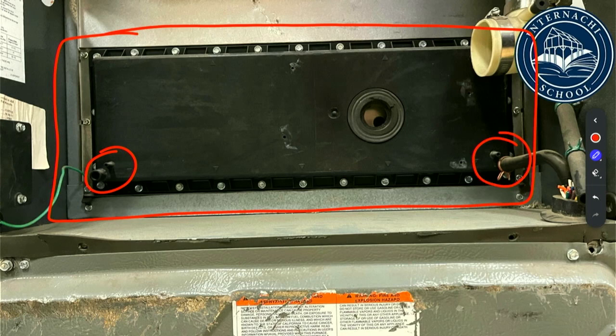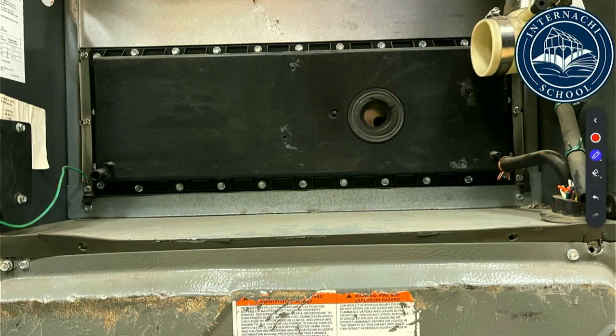This is another good clue for us: if you can see any of this condensate that's draining and it's got rust and crud in it, this thing is pretty much done at that point. It should be clear, clean liquid going down there. If it's dirty in any way, push that off to a heating contractor and let people know there's a good possibility it might have to be replaced. We're not going to know for sure until you can pull it out and see it, and that's beyond our scope, but it's still a good indicator for us.